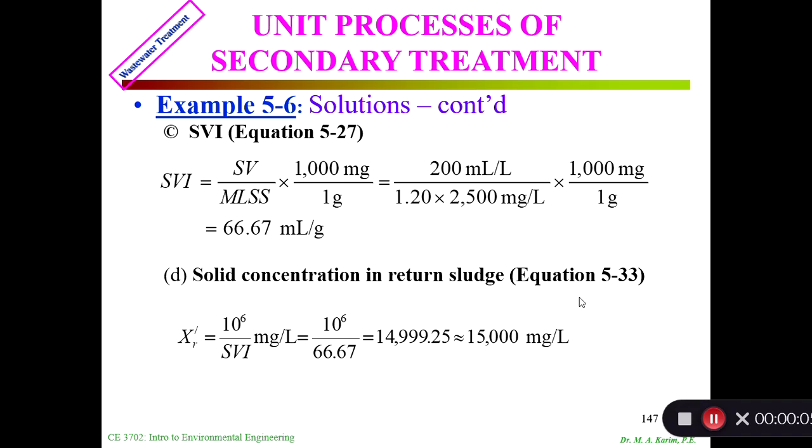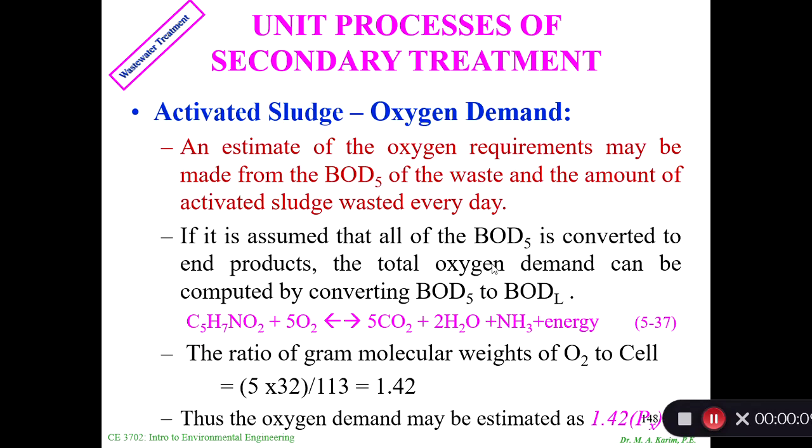Let's start from slide 148. Now we are going to see how the oxygen demand is calculated. Oxygen demand is necessary because we want to do aeration in the activated sludge aeration tank. An estimate of oxygen requirements may be made from the BOD5 of the waste and the amount of activated sludge wasted every day. If it is assumed that all the BOD5 is converted to end products, the total oxygen demand can be computed by converting BOD5 to BOD ultimate.